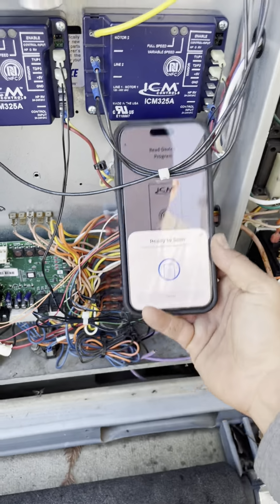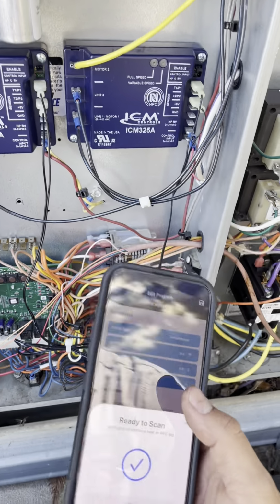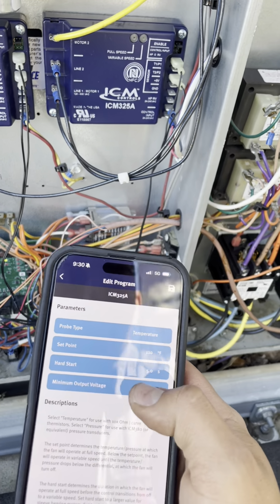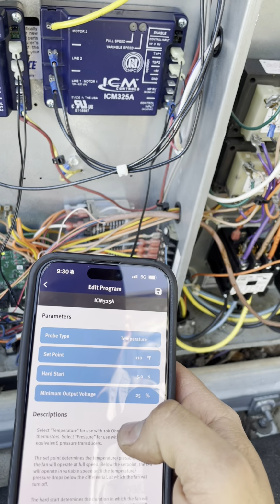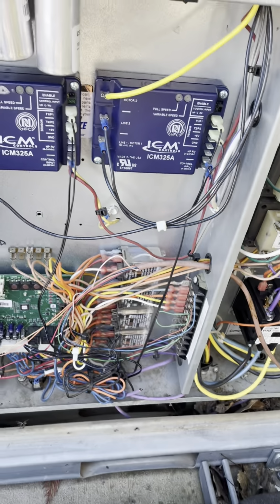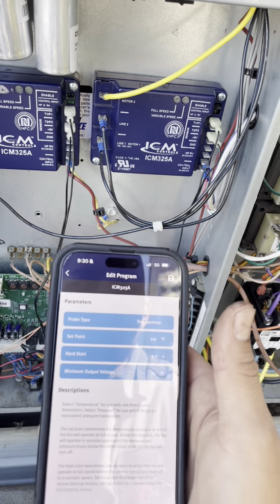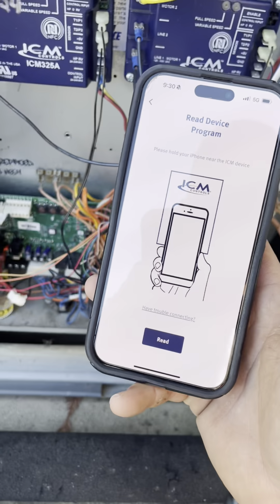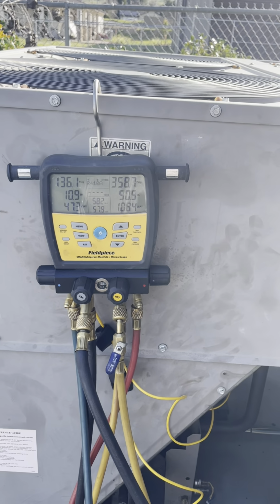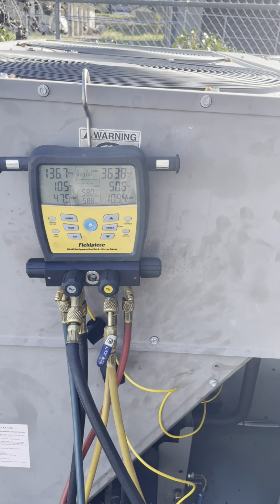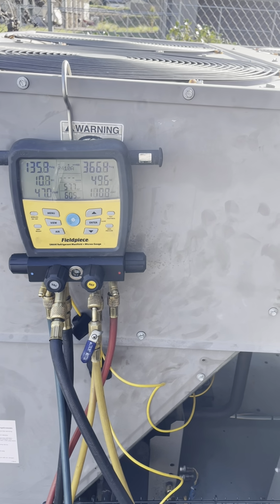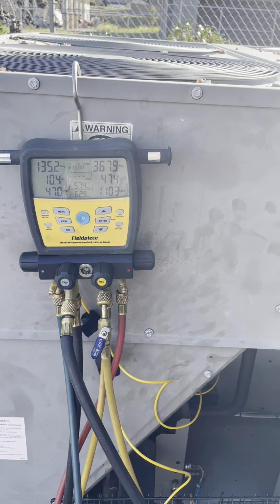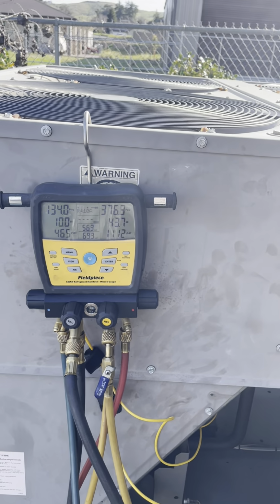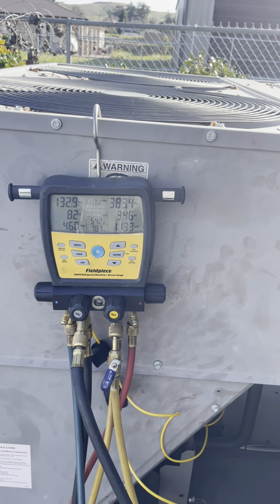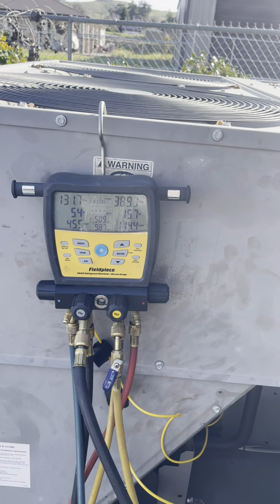So scanning this one's the same thing. I changed it already. The only adjustment I made was changing the set point to 110 because that's what we want to maintain on our liquid line saturation temperature. So pretty cool. I didn't know that. So I just turned on this. I only increase the temperature enough to turn on one circuit. So let's see. We got one compressor running right now. It's registering about 110 degrees. Should be kicking on the fans.